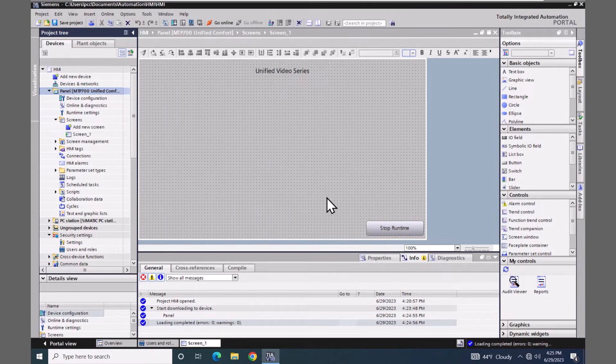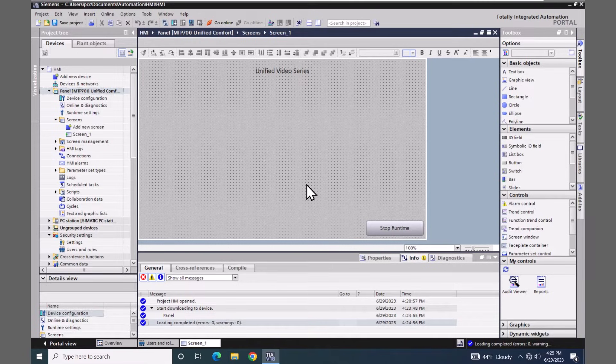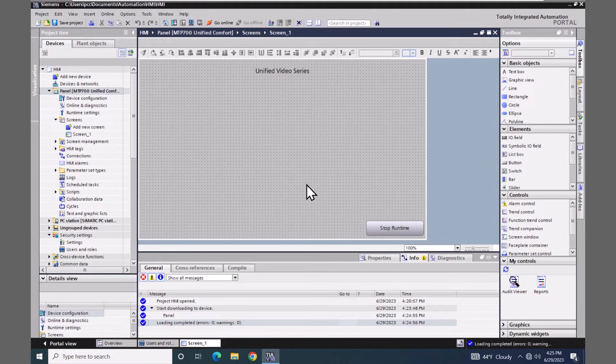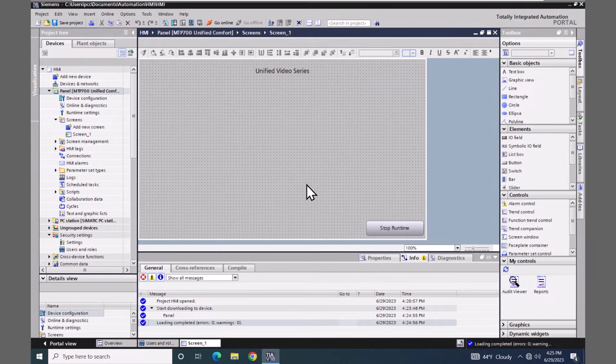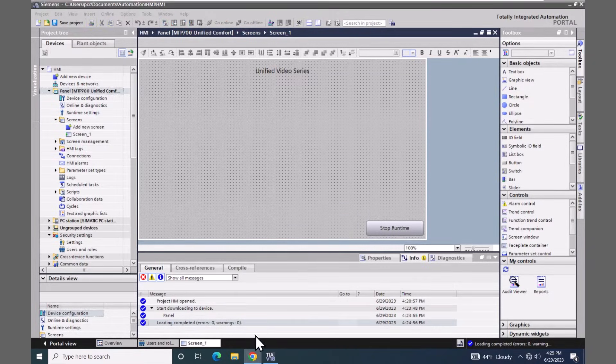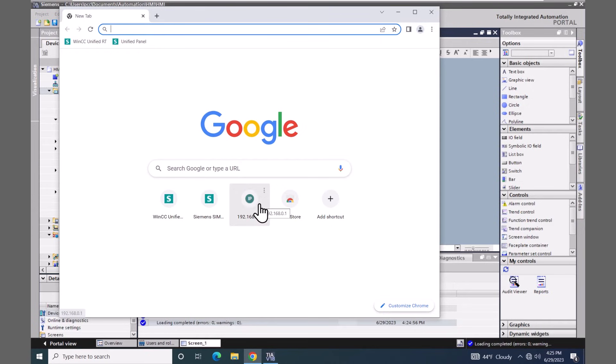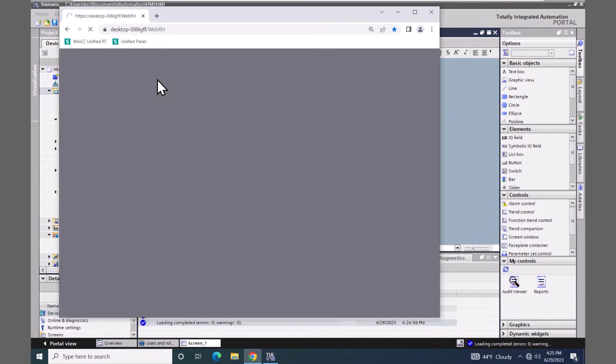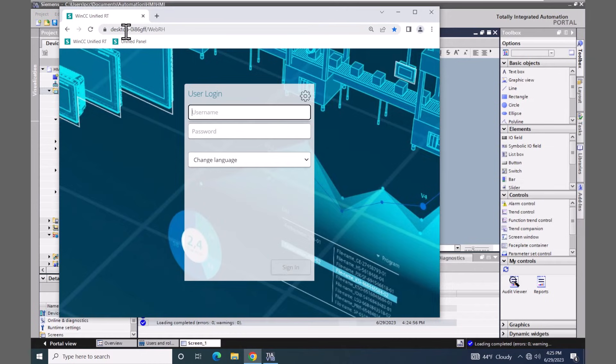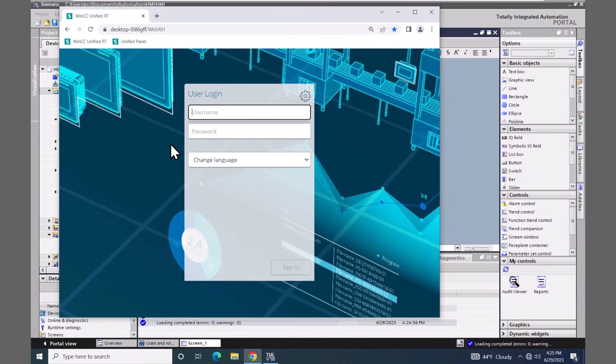Now one of the things that you will notice is when the simulation is started, it compiles and it downloads, but you don't have any visual representation of your HMI at this point in time. That's because we need to start a browser to log into the runtime system. I'm going to use the Chrome browser and I have a bookmark that is set up. It's the computer name forward slash webrh to access the runtime system.